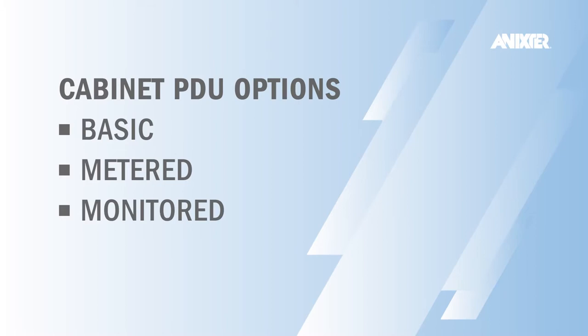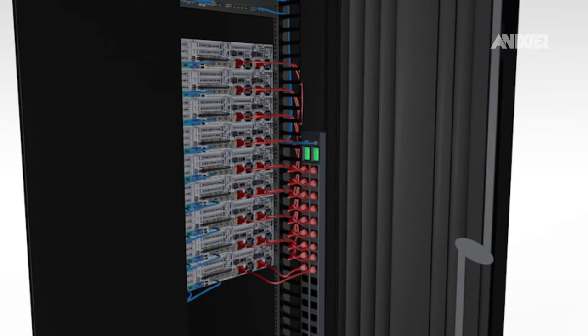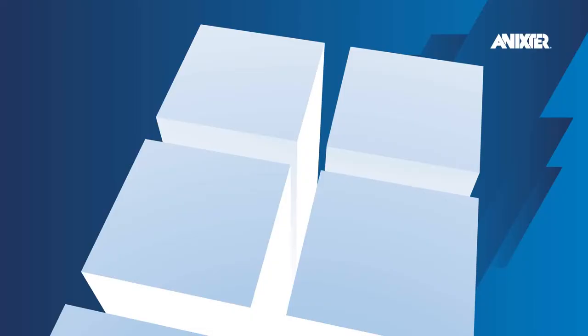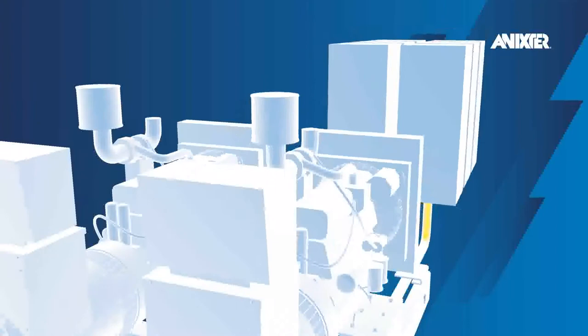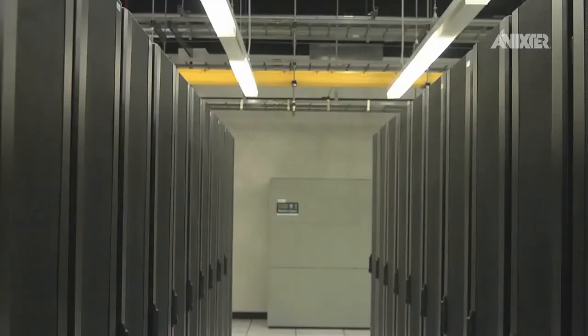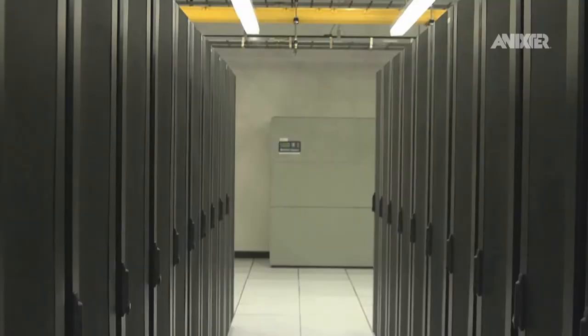Real-time controlled monitoring, which can be down to the individual outlet, provides you with the data needed to efficiently manage your data center's power at the cabinet or individual IT component, reducing the risk of downtime. As a best practice, delivering higher voltage to the cabinet PDU will further optimize your power distribution architecture by reducing energy loss caused by various power conversions and allow for further operational efficiency gains with your IT equipment.